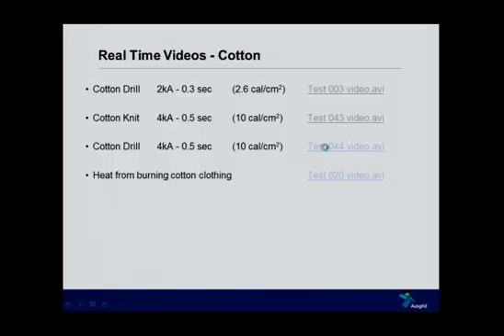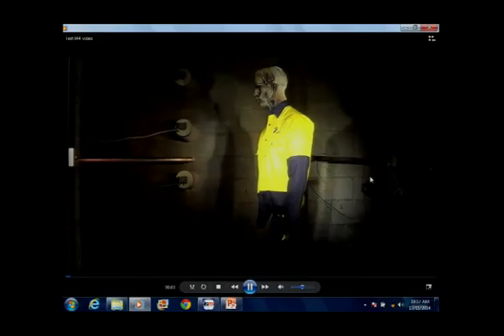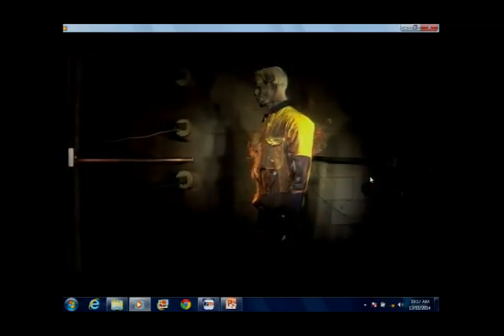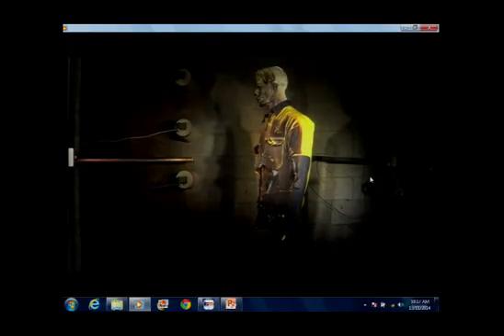So let's put that myth to the test. You'll see that there is more of the shirt left initially after the arc. Same fault, 4 kA for half a second, an average measured energy between 10 and 11 calories. So you'll see that there is more that survived the arc, but it's all now more material that's been brought up to flashpoint and is continuing to burn on the mannequin.